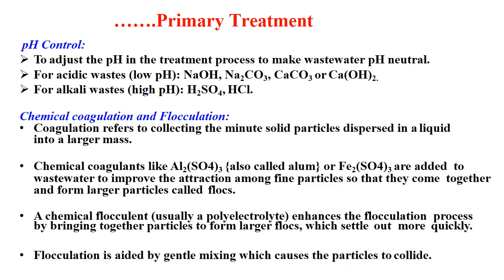Chemical coagulation and flocculation: coagulation refers to collecting smaller solid particles dispersed in a liquid into a larger mass. Chemical coagulants like aluminum sulfate (alum) and ferric sulfate are added to wastewater to improve attraction among fine particles so they form larger masses called floc. A chemical flocculant, usually a polyelectrolyte, enhances flocculation by bringing particles together to form larger flocs that settle out more quickly. Coagulation is aided by gentle mixing which causes the particles to collide.